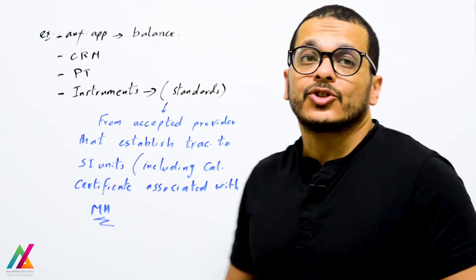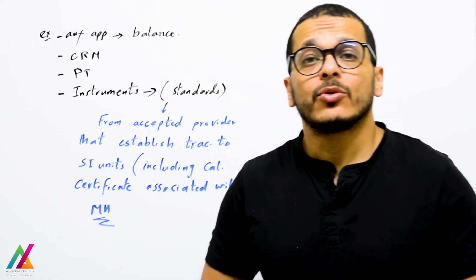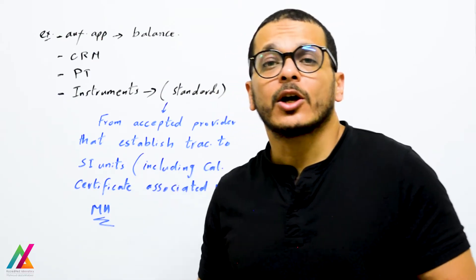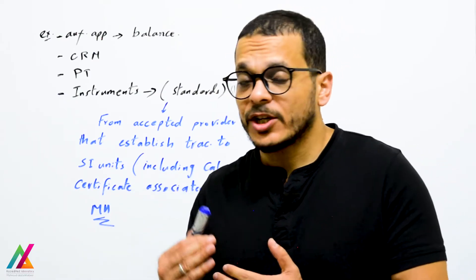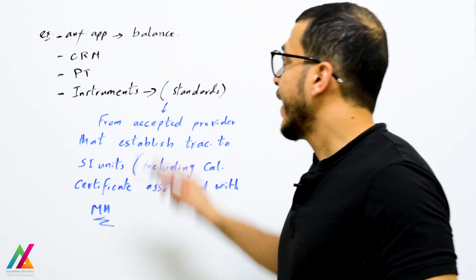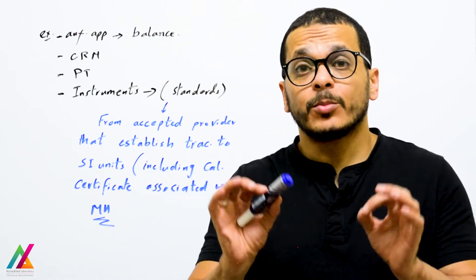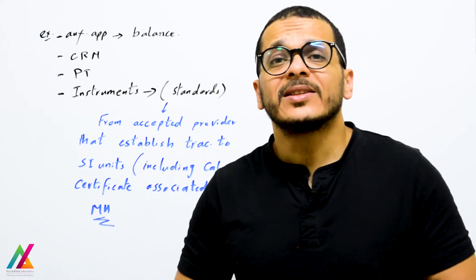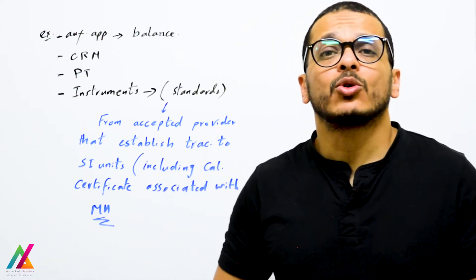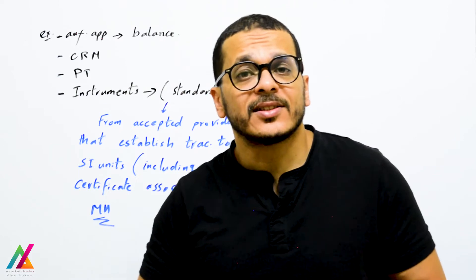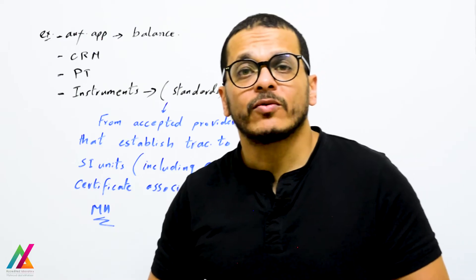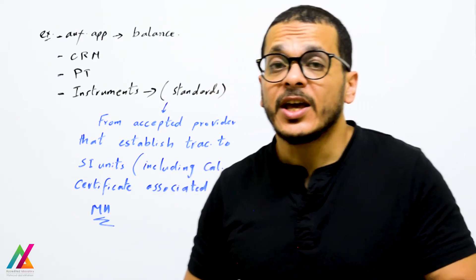As an example, auxiliary equipment such as a balance is calibrated using calibrated weights, which are calibrated by a competent calibration lab traceable to the National Metrological Institute, which is traceable to SI units. Certified Reference Materials (CRM) shall be provided by a specific provider meeting the requirements of ISO/IEC 17034, and Proficiency Testing (PT) samples shall be provided by a specific provider meeting the requirements of ISO/IEC 17043.